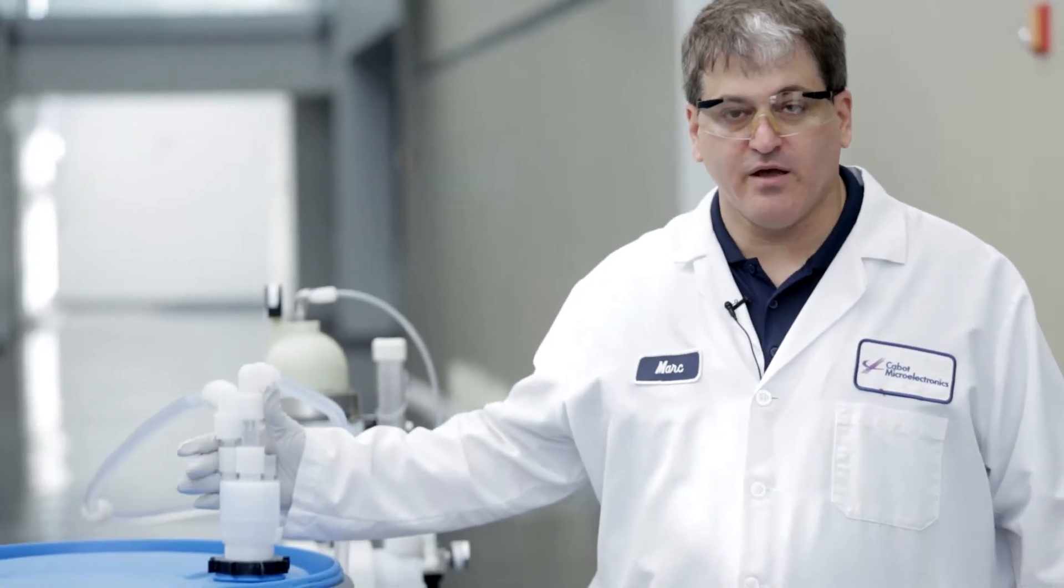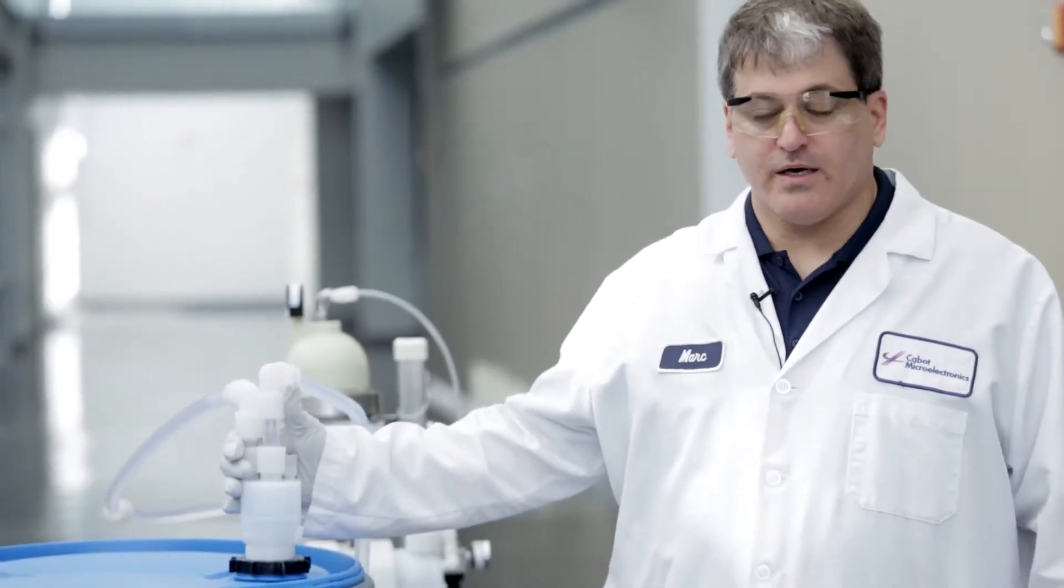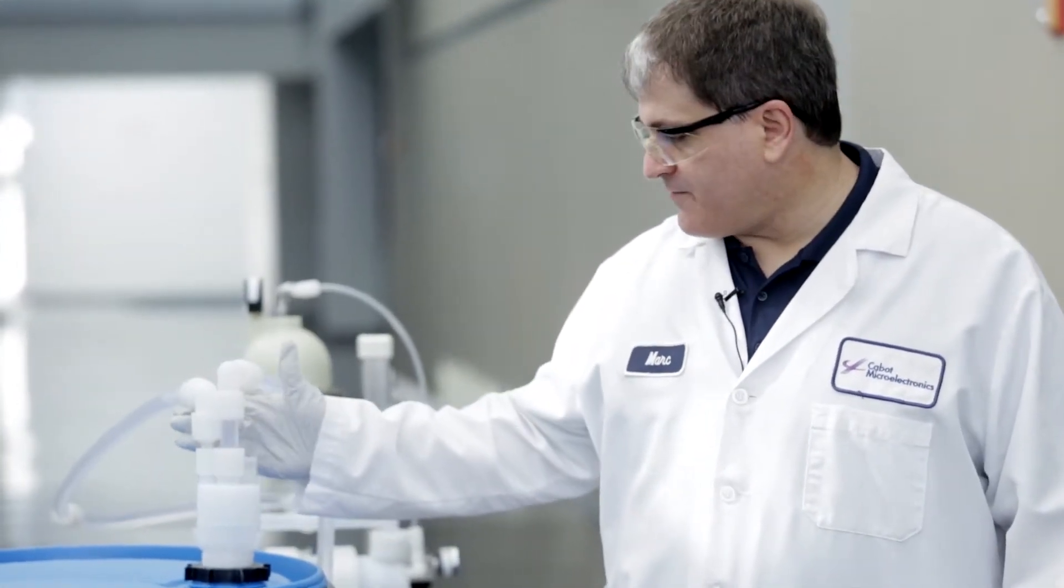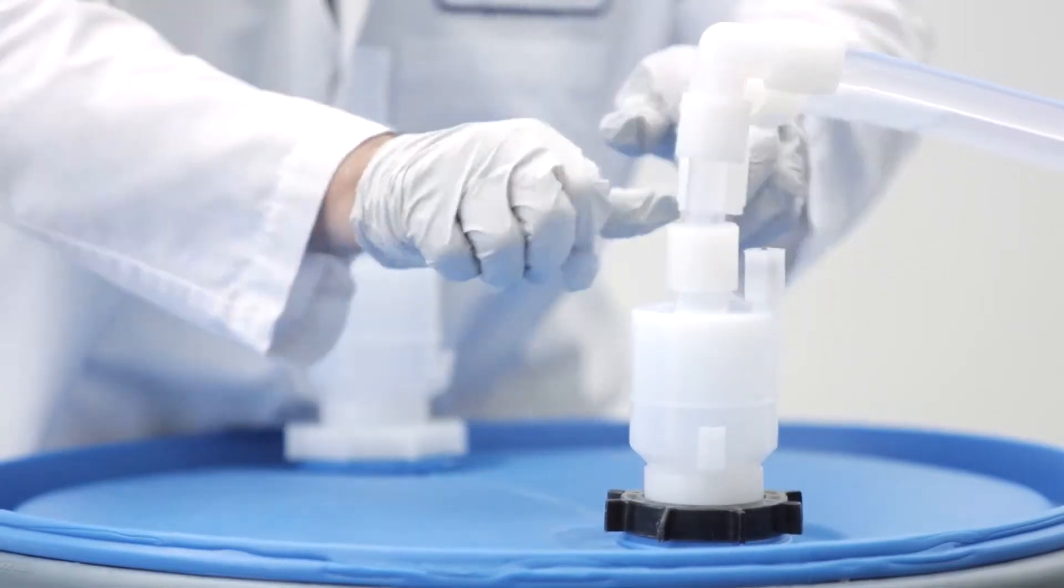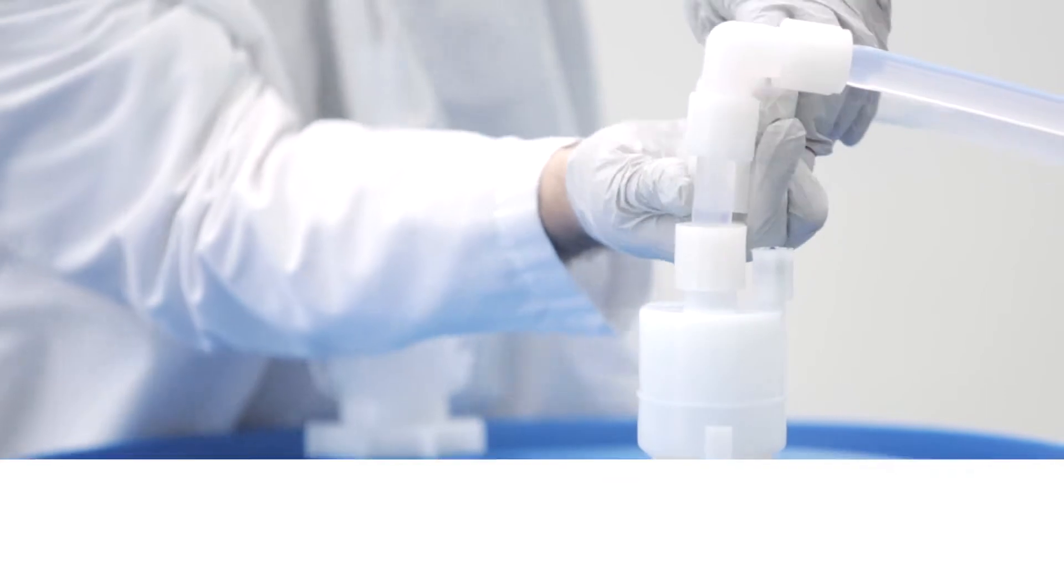As we discussed earlier, there is a thing that I've seen in the industry a lot and that's using a QC2 dispense head for both feed and return. It's not something we recommend, especially for slurries that can be sensitive to shear damage. And I've reconfigured my apparatus here to show you exactly why we don't like that and why it's a bad idea.